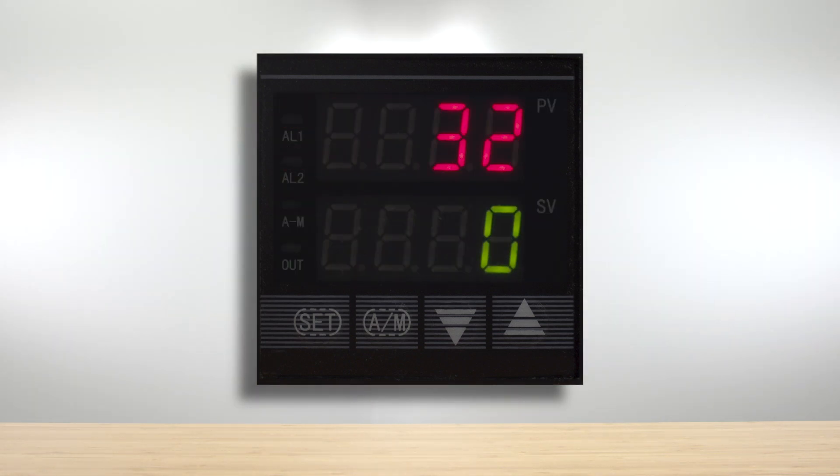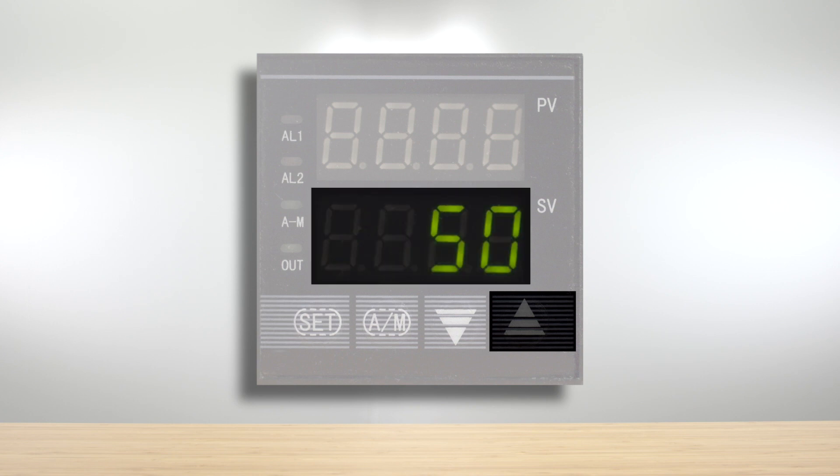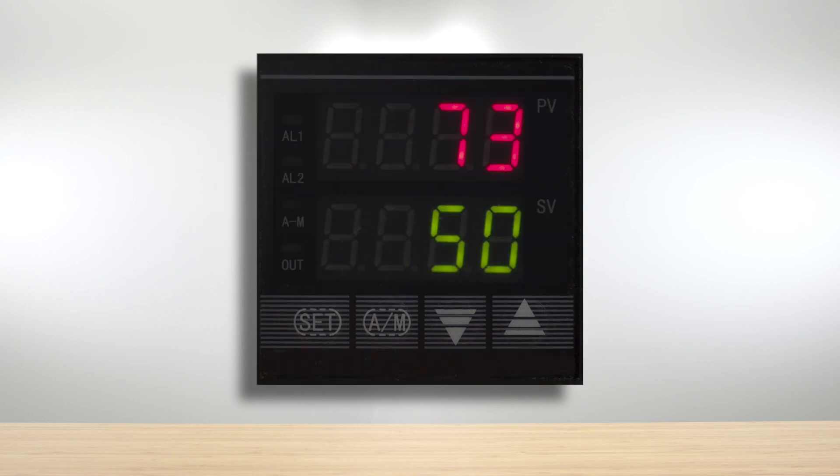We're going to turn the unit on. So at this point your unit should be flashing stop. If it's not you want to hold the up arrow for two to three seconds until it says stop. You always want to keep the unit in stop mode when you're not in use because if you put it in to run it's actually going to heat up on you.